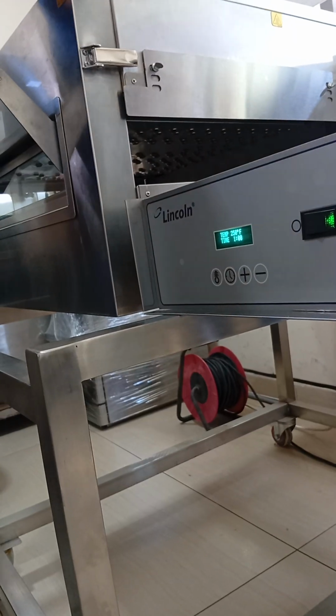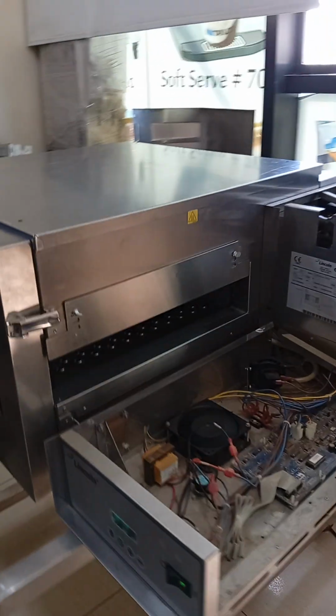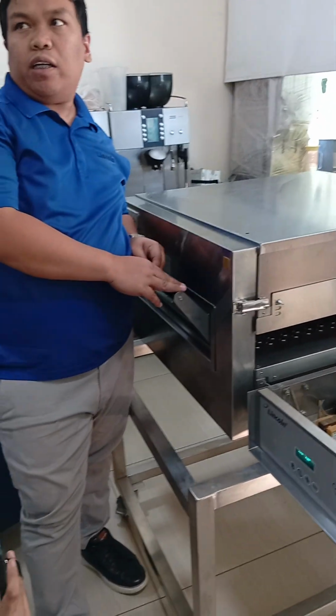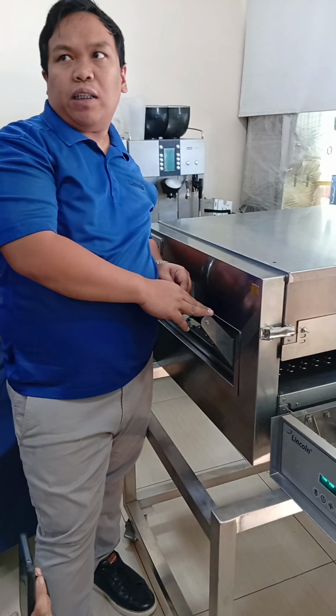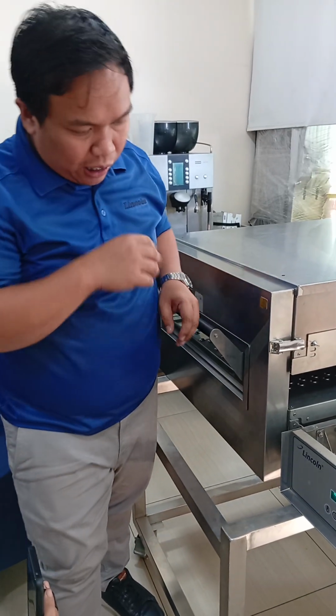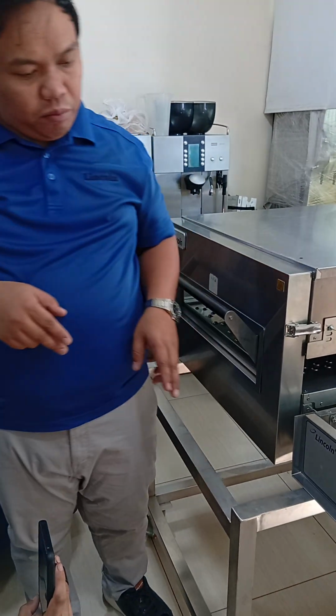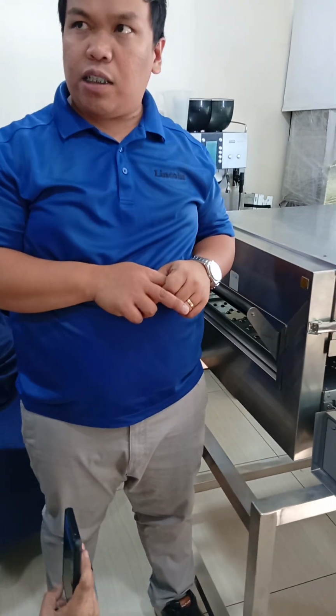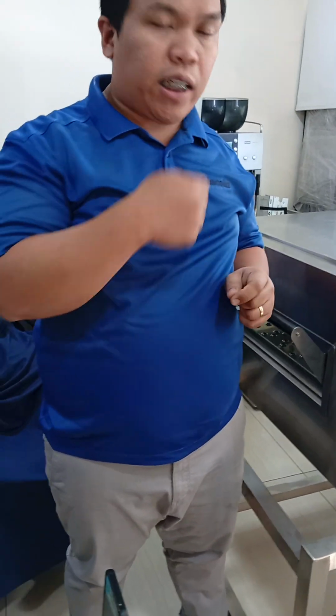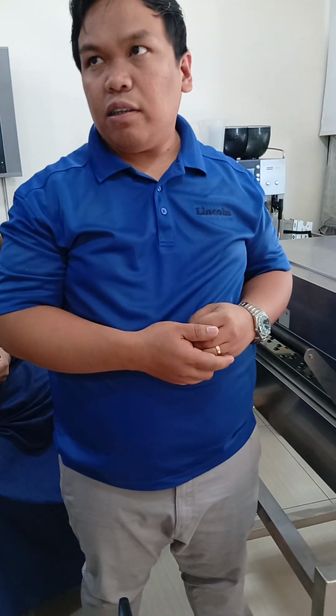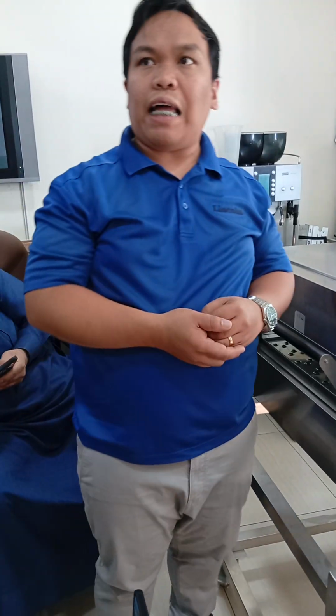Okay. What if I have more than 20-degree difference from the actual to the display? You can calibrate the probe. So you can calibrate that. Okay. During the calibration, you need to adjust the offset. Yes. But how will you check again to confirm if your offset is correct? By temperature. The standard is you need to wait at least 30 minutes for the temperature to stabilize. Okay?